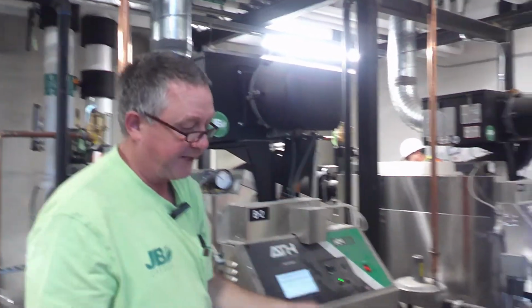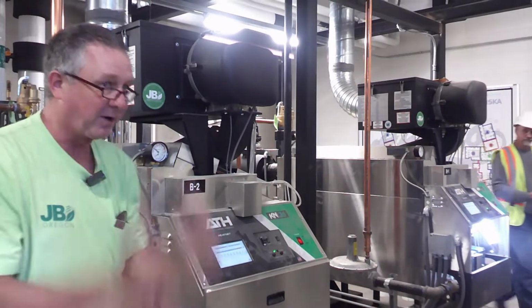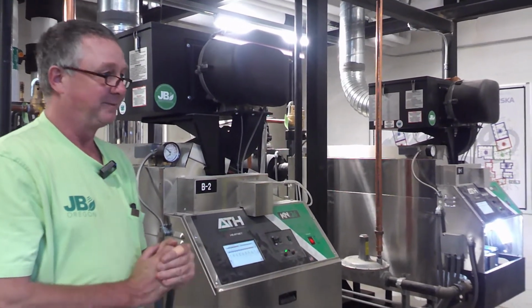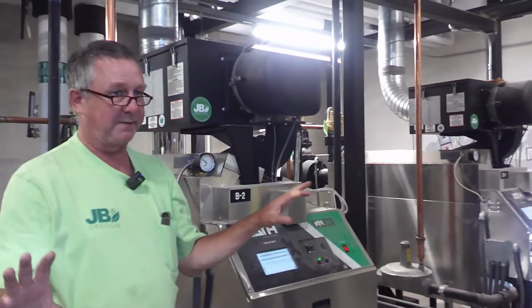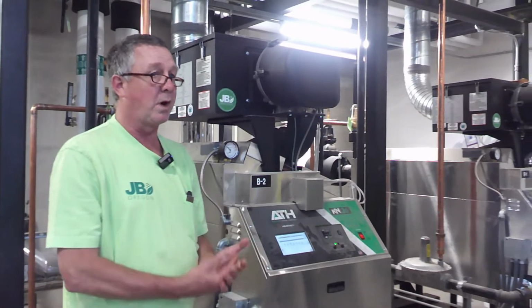I call it the tap test. I tap it on the ground gently. It's got a metal frame around it. If you start wailing on it, that frame comes off, you are not putting it back together. You're not. So just gentle tap, and if you see a cloud come off, it's time to clean or replace the filter.